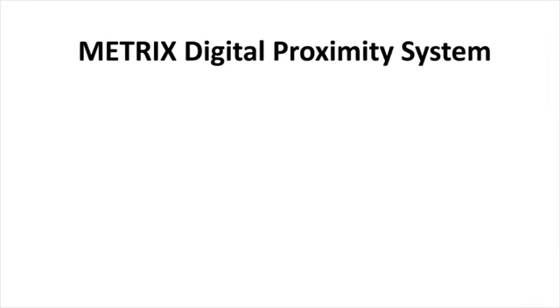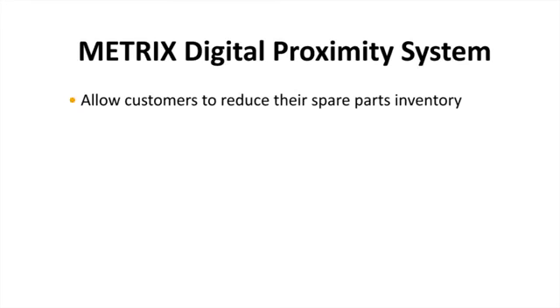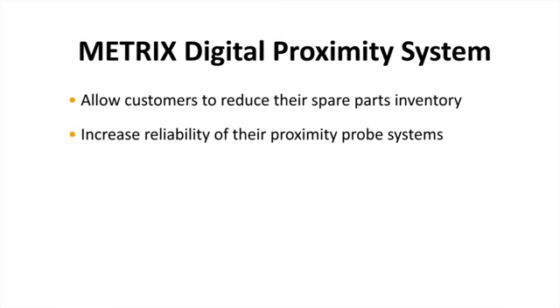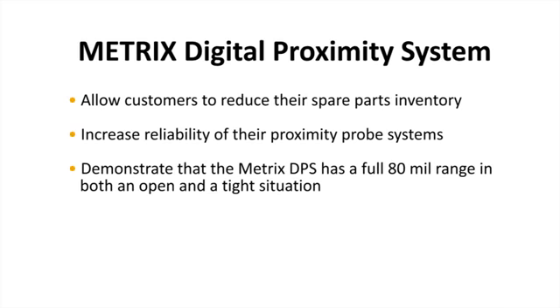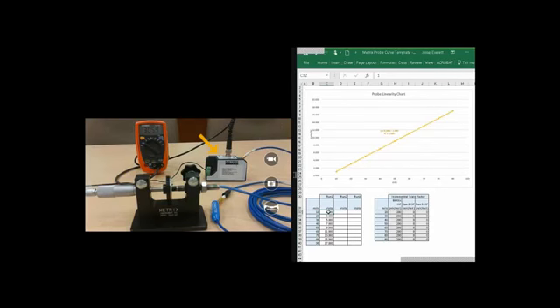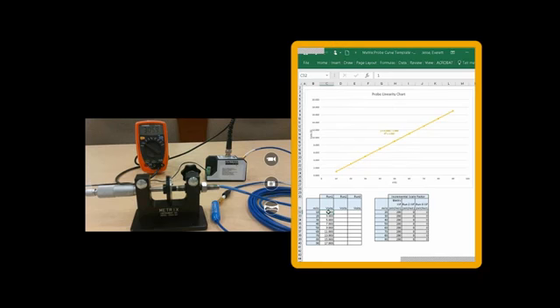The purpose of the Metrix Digital Proximity System, or DPS, is to allow customers to reduce their spare parts inventory and increase the reliability of their proximity probe systems. This video will demonstrate that the Metrix DPS has a full 80 mil range in both an open and a tight situation. We will demonstrate the linearity of the Metrix DPS using a static calibrator with a 4140 steel target, a standard Metrix MX8030 probe and extension cable, a multimeter to display gap voltage, and Excel to record our data.